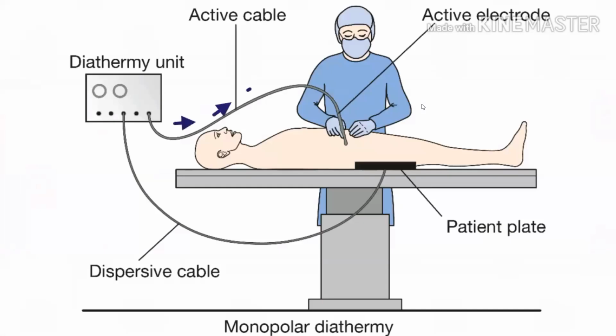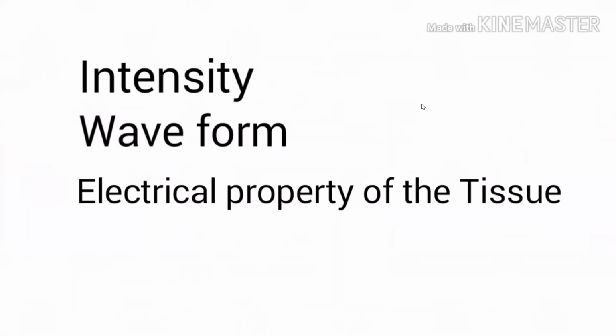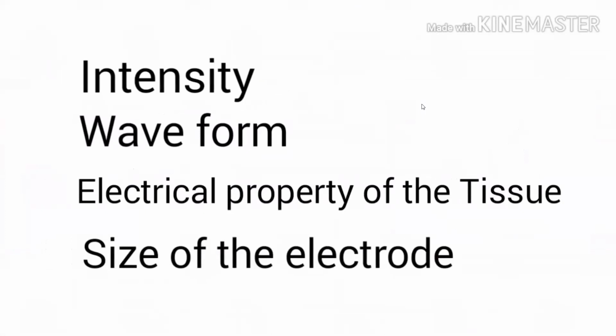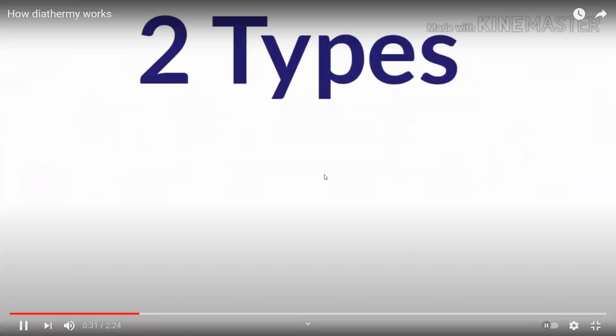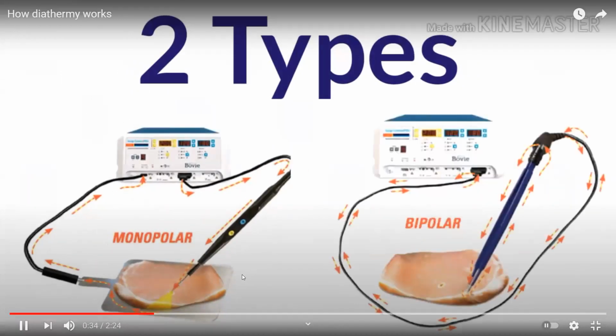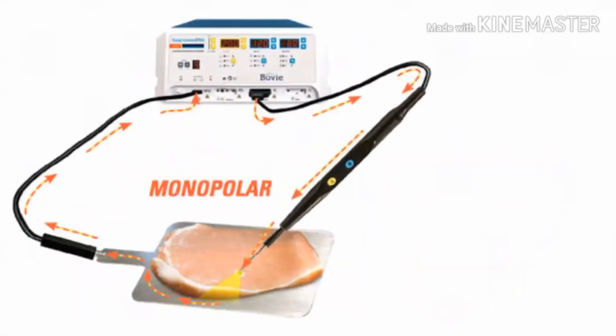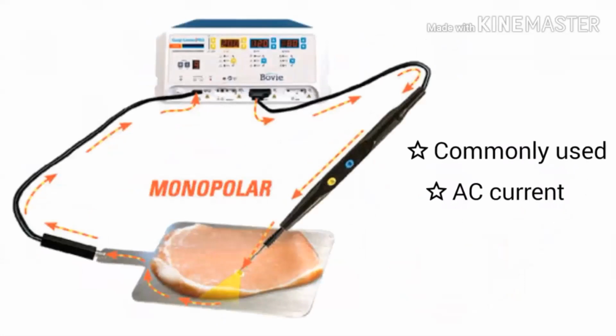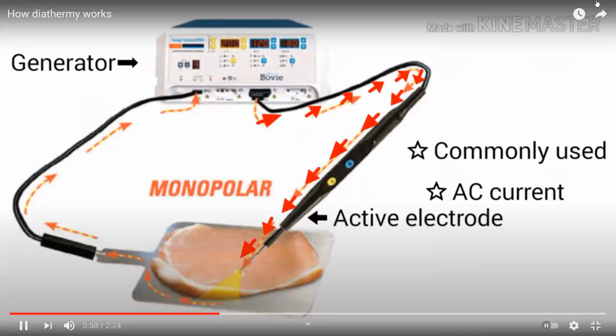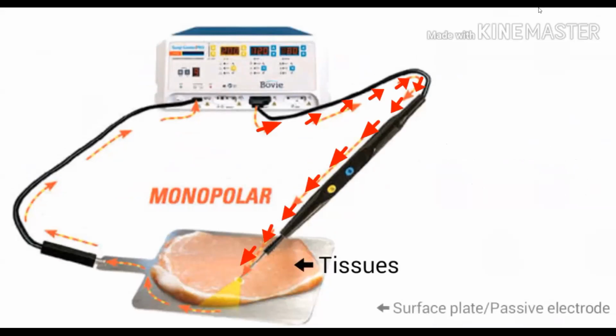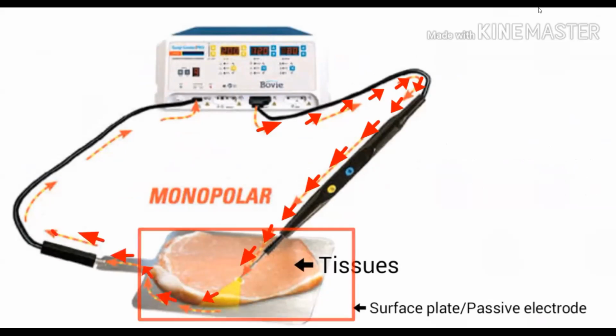When an electrical current passes through a conductor, some of its energy appears as heat. The heat produced depends on the intensity of the current, the waveform of the current, the electrical property of the tissues through which the current passes, and the relative sizes of the two electrodes. There are two basic types of diathermy system in use: monopolar diathermy and bipolar diathermy. In monopolar diathermy, which is the most commonly used form, an alternating current is produced by a suitable generator and passed to the patient via an active electrode which has a very small surface area. The current then passes through the tissues and returns via a very large surface plate, the passive electrode, back to the earth pole of the generator.